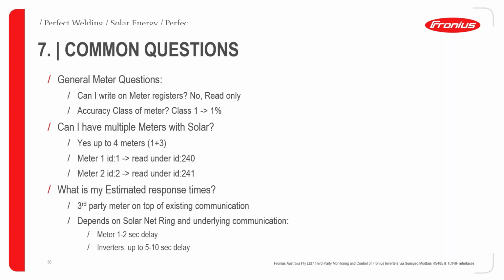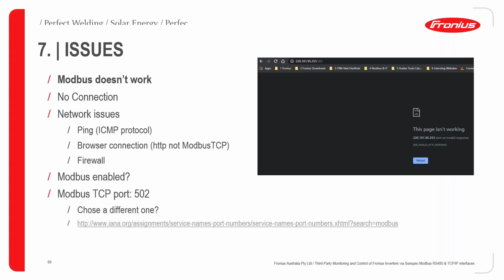For example, if you have 50 inverters and you want quicker times, maybe 4 or 5 data manager cards can satisfy your timing needs. In this situation, bear in mind, only one of those will have a meter connected. You don't have to have a meter connected across all of them for the data to show properly on SolarWeb.